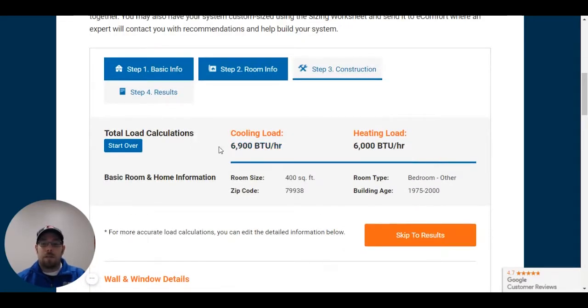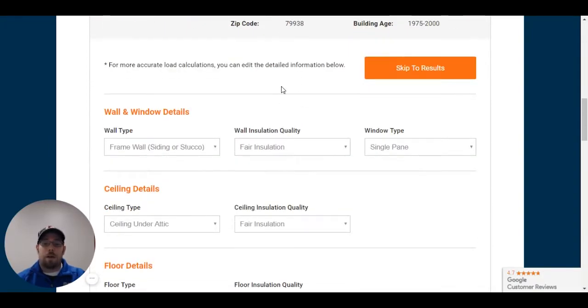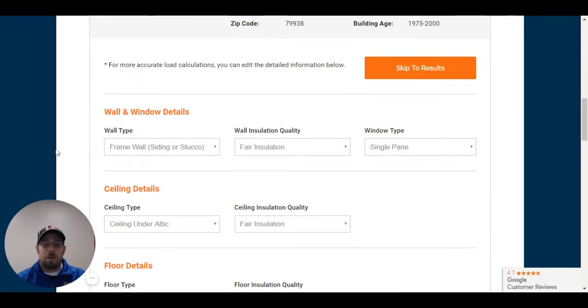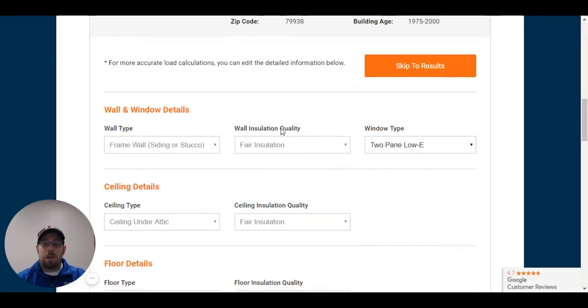Continuing on, 6900 BTUs to 6000. That's changed it a little bit, but not quite too much. So I know that the frame wall was stucco for where that's located. Insulation, I'm going to keep it as fair for the walls. The windows I know are two pane low E.